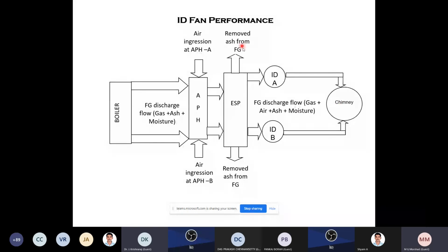So if the air is not removed properly, if ash is not removed properly, what will happen? If the performance of the ESP is very poor, automatically the ID fan will be loaded. The ID fan will see higher loading. It may trip sometimes. And at the same time, your auxiliary power consumption will also increase. Suppose your fuel has very high ash content, very high sand content. What will happen? The ESP will not be able to extract all the required weight of ash or sand from the flue gas. So automatically the ID fan and FD fan will also be loaded. So the performance of the ESP, and the quality of the fuel, are also very important for auxiliary power consumption.